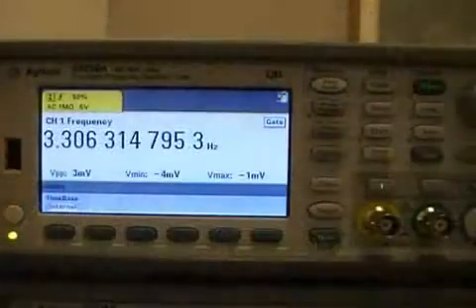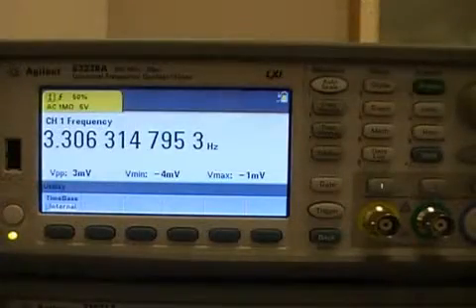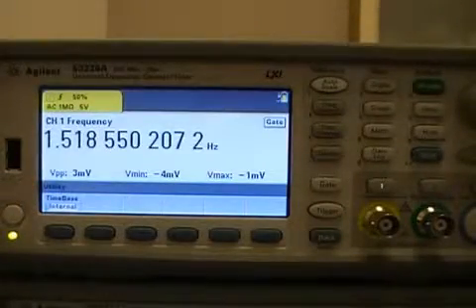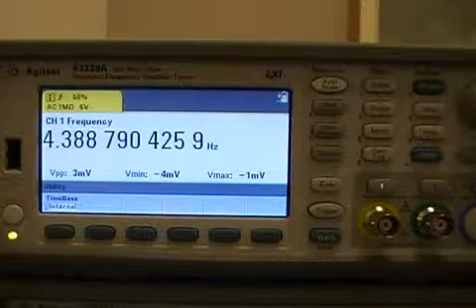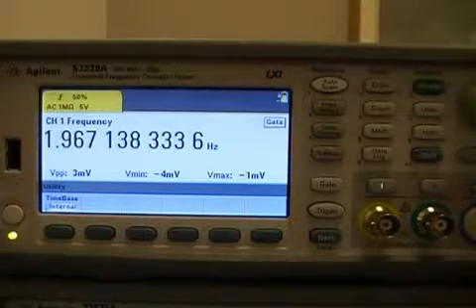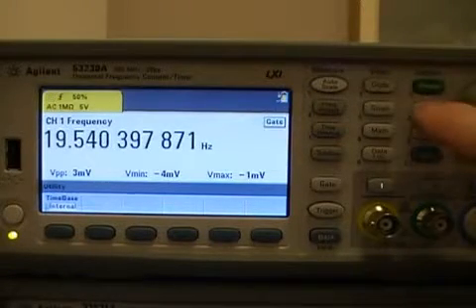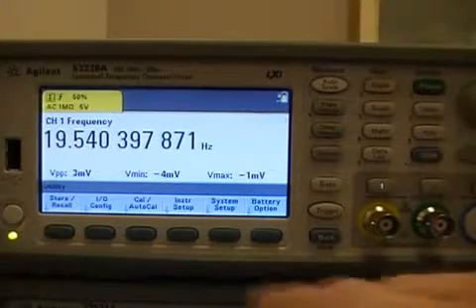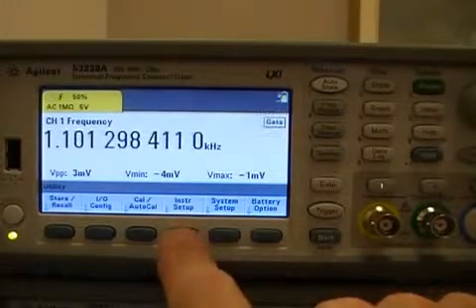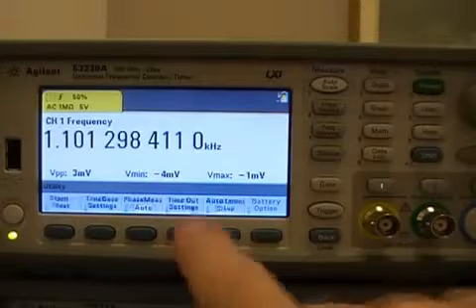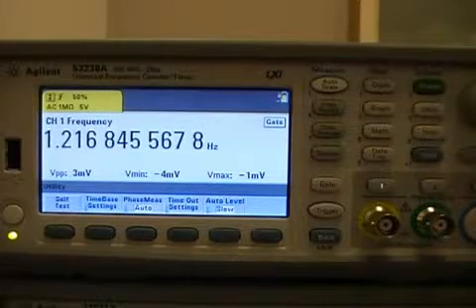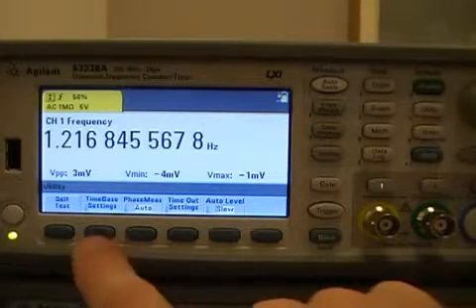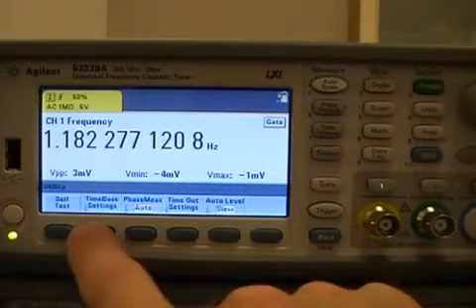With the external reference signal connected to the rear terminal of the instrument, set the external reference source by first selecting the utility key, followed by the instrument setup soft key. From the instrument setup menu, select time base settings.